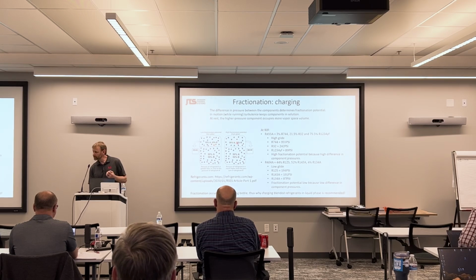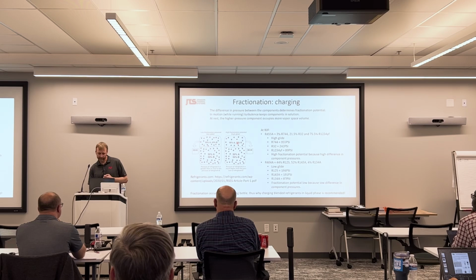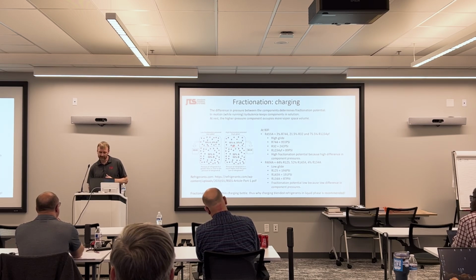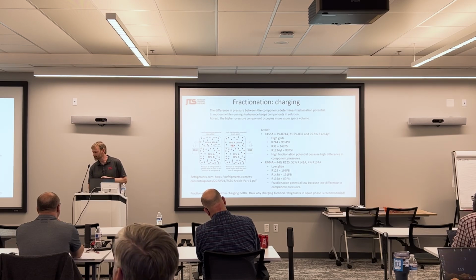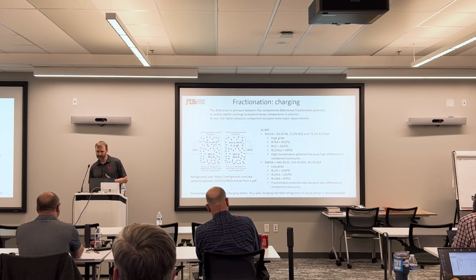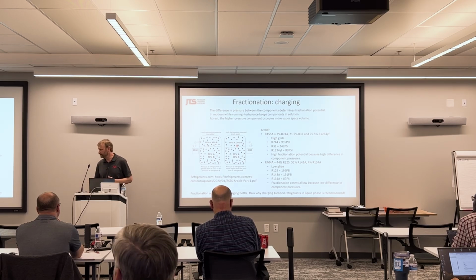Now, if the refrigerant that you're using happens to have high glide, that gets amplified. With a high glide refrigerant, you're going to end up pulling 80% of component A into the system and 20% of component B. So, if you're charging with vapor, it probably doesn't matter if you plan on using the whole container. It's all going to end up in the system and get mixed together. But honestly, if you're going to put a whole container into the system, it's a lot quicker to do it with liquid.